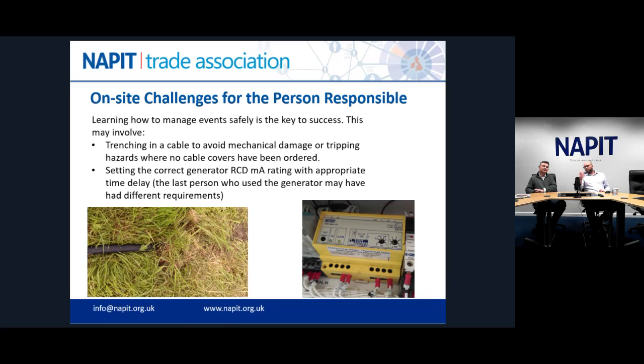Then just to bring in the RCD there, we could have a generator turn up on site and it has come out of the generator yard, set to 30 milliamps. Is that always going to be suitable? No, because what tends to happen is a lot of modern loads, things like LED lights and similar, the power supplies leak a little bit of current. There's natural leakage, which is perfectly acceptable, and it's a design aspect of the filtering components in them. But what that means is that if you have 20 of these lights and you connect them all onto that RCD, that amount of leakage will push the RCD over its operating limit, and it will keep nuisance tripping, basically.